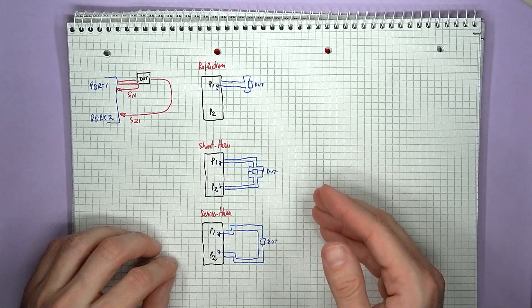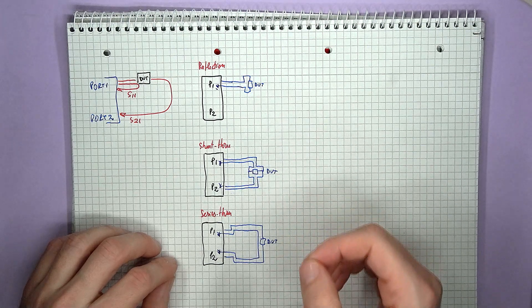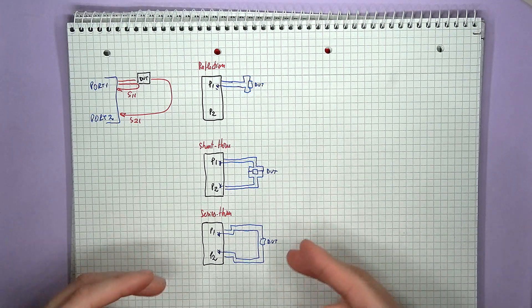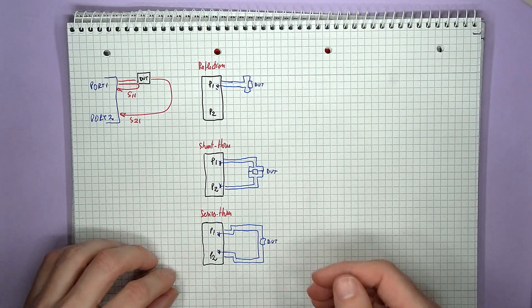and then you have the two-port measurements, where the tested circuit is either shunted in between the signal line and the ground, the shunt through setup, or the test component is placed in series in between the two ports, the series through setup.